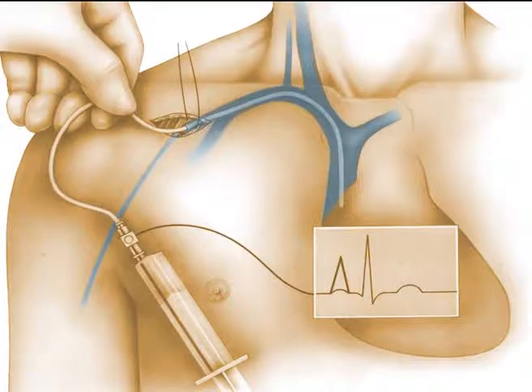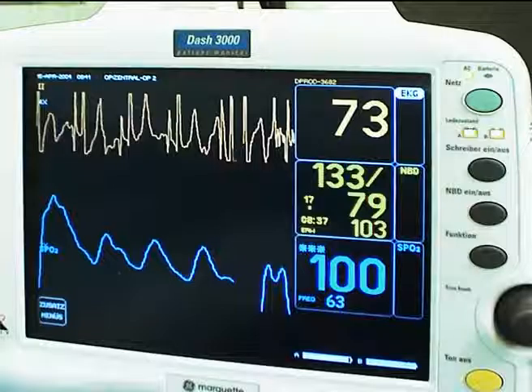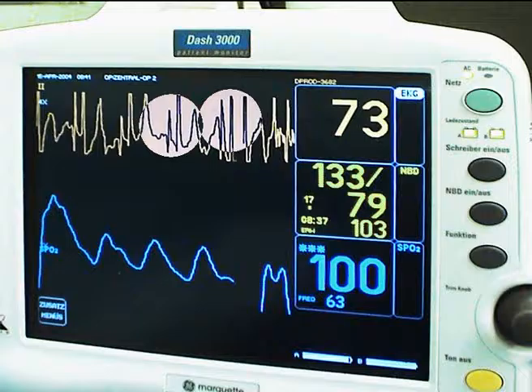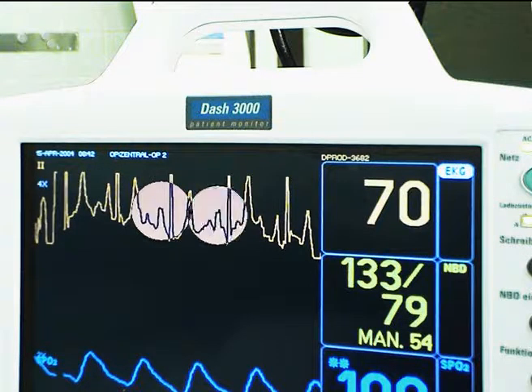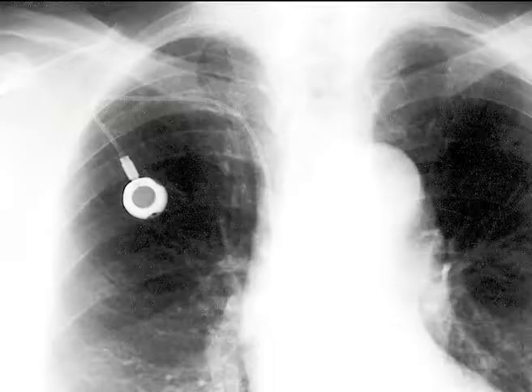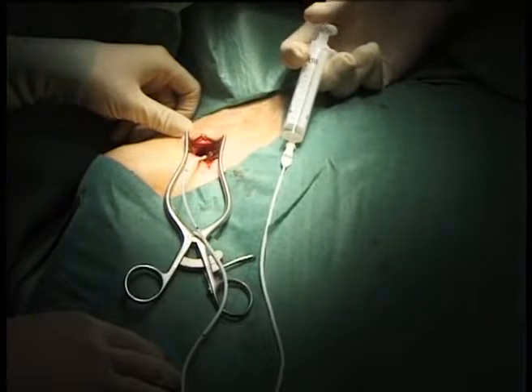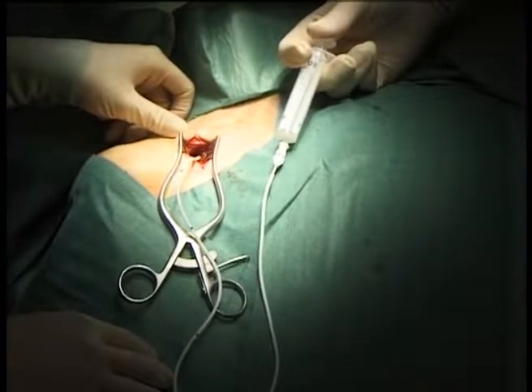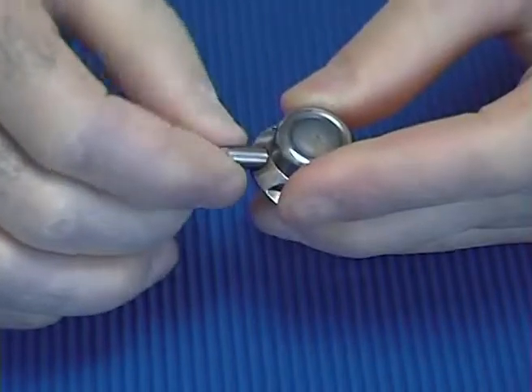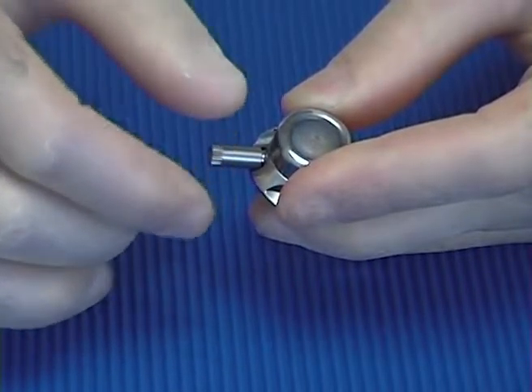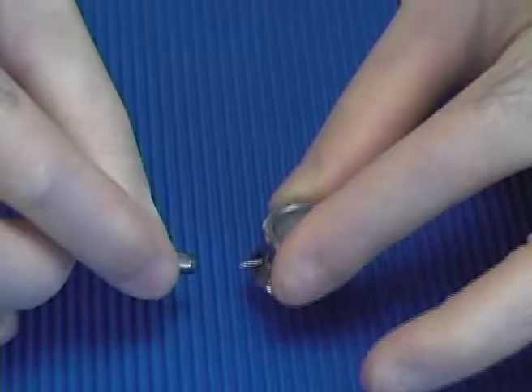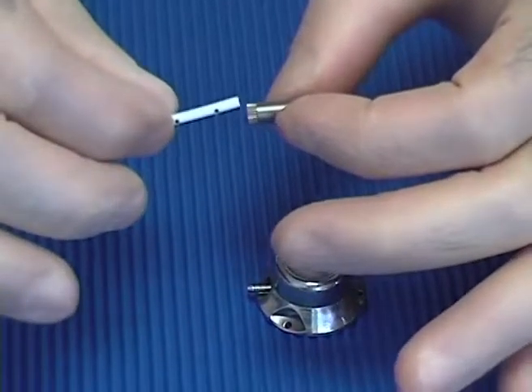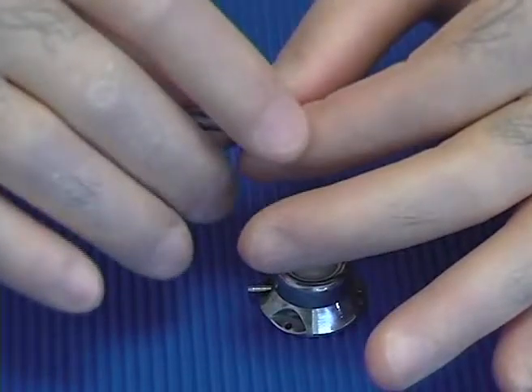The position of the catheter tip is confirmed by means of image intensification, but can be determined more easily by intraatrial EKG electrode tracing. The need for a postoperative X-ray within 6 hours represents a mandatory legal requirement to recognize incorrect catheter placement. The port chamber is filled, surplus catheter is trimmed off. The catheter should be clamped with an atraumatic clamp prior to trimming to prevent air embolism. The catheter is then connected to the port chamber by advancing the sleeve over the catheter, which is then screwed to the port under gentle traction.